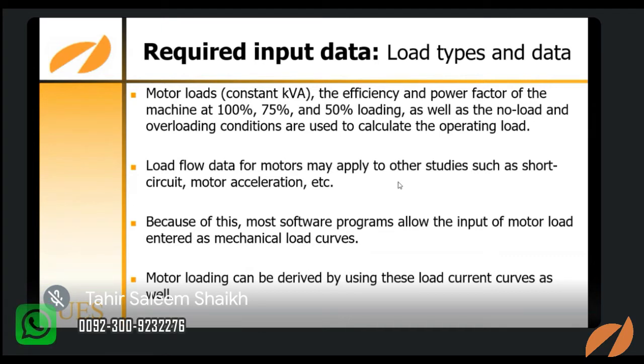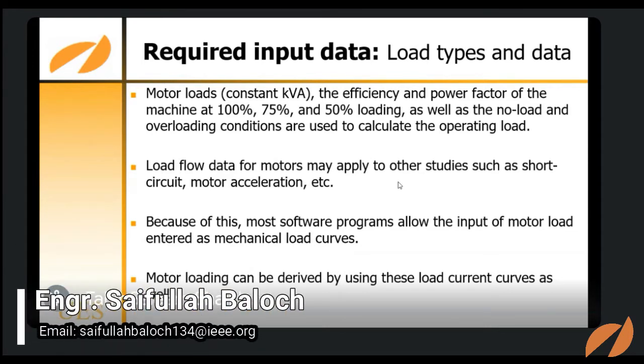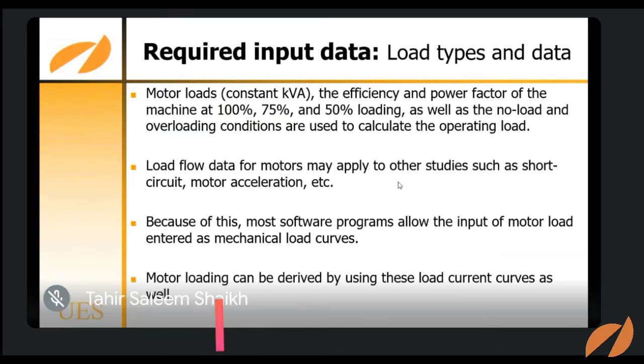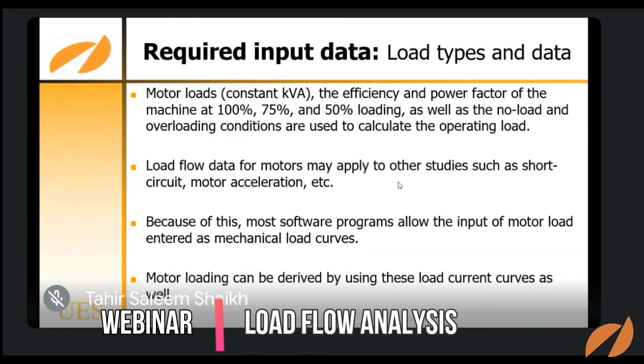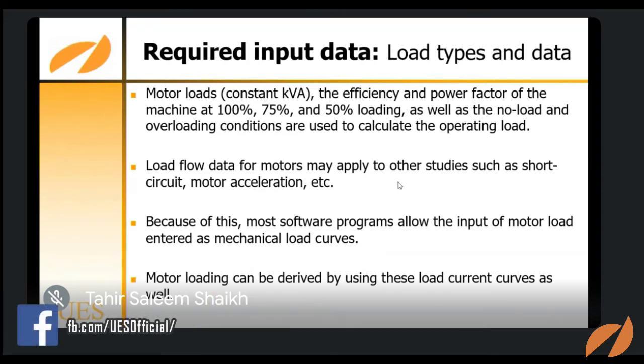Because of this, most software allows the input of motor load entered as mechanical load curves. Most of the time, if you are using any software having load flow calculation for motors especially, it may ask you for the motor mechanical input and output power. If you have such software, you need to have such data according to the needs of that software. Motor loading can be derived by using these load curves as well.